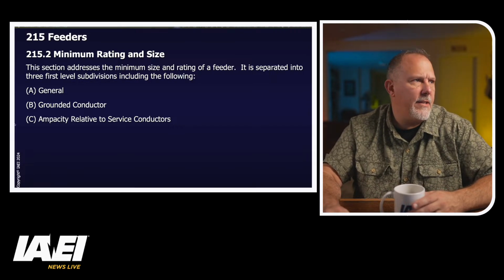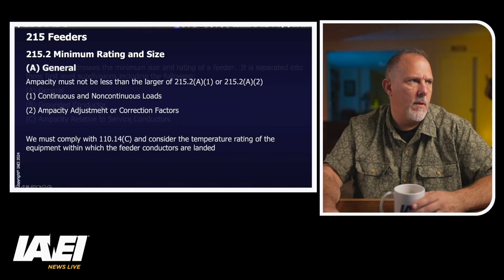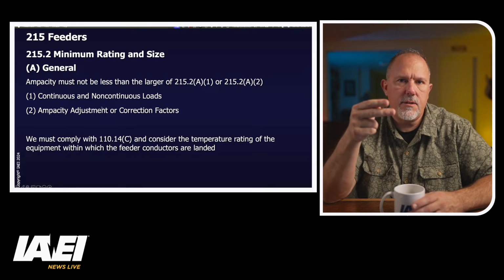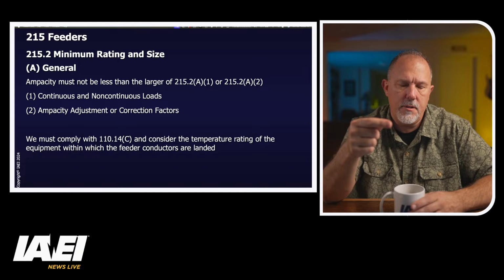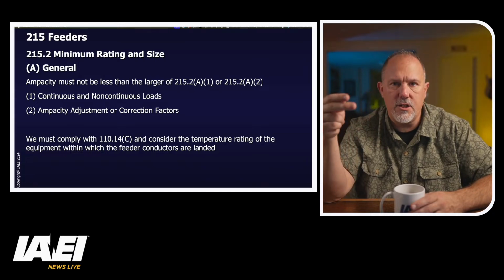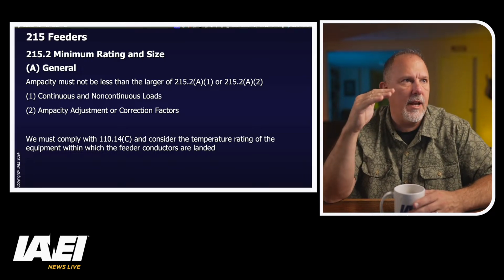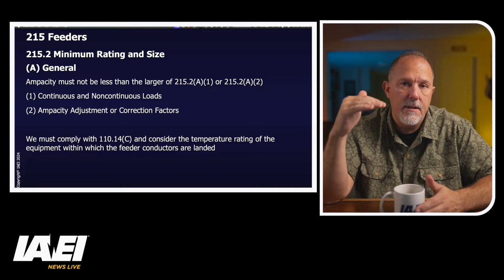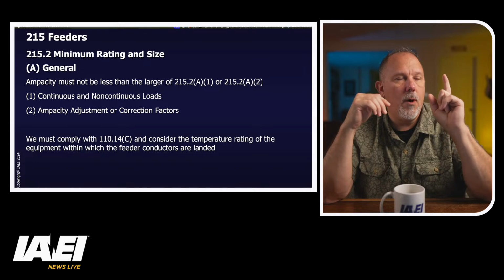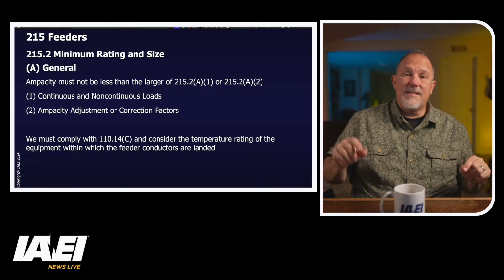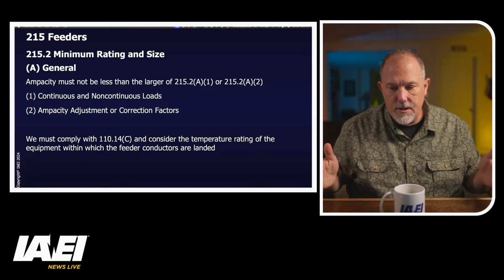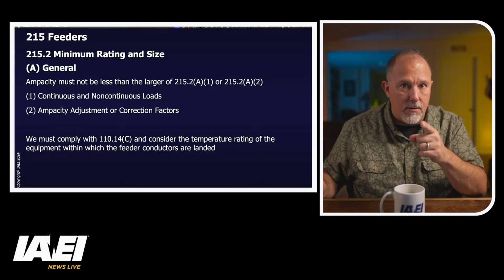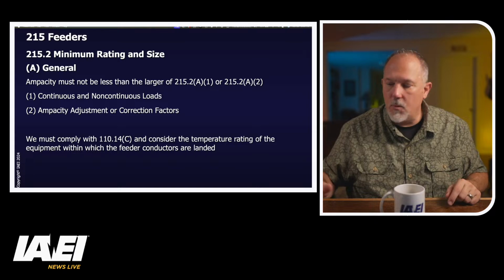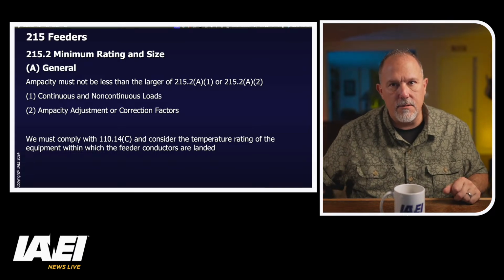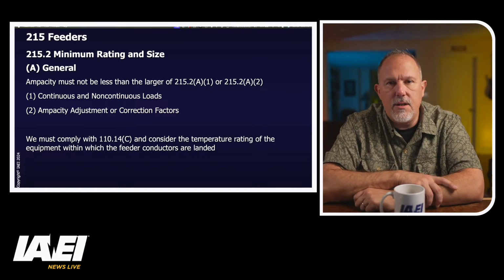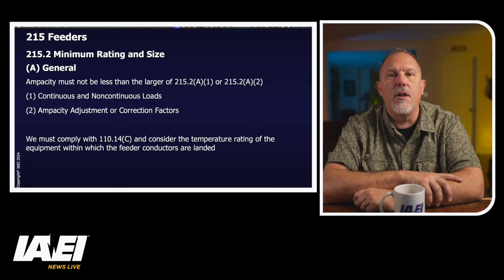All right, so what I do in A is I have to do two calculations. One, I do the continuous and non-continuous loads. And two, I do the ampacity adjustment or correction factors, and whichever one gives me the larger ampacity that I need tells me what will suffice for the conductor itself. I haven't determined the overall ampacity of my feeder until I consider 110.14, which is the equipment within which I'm landing a conductor.